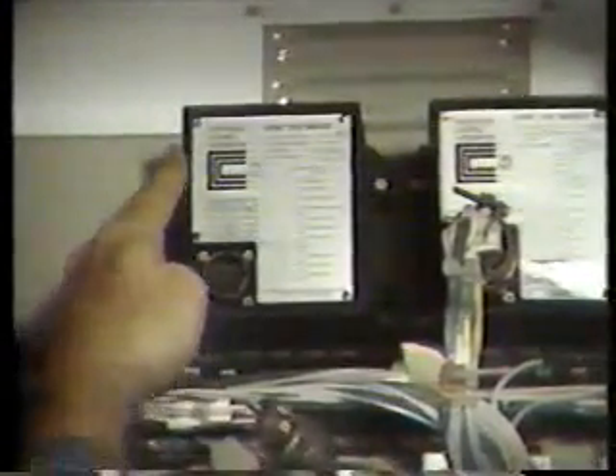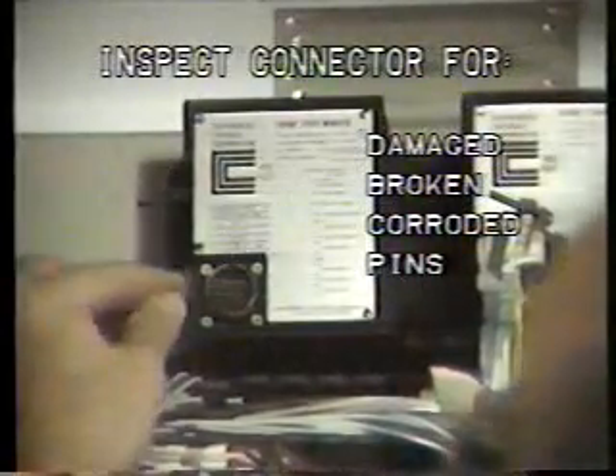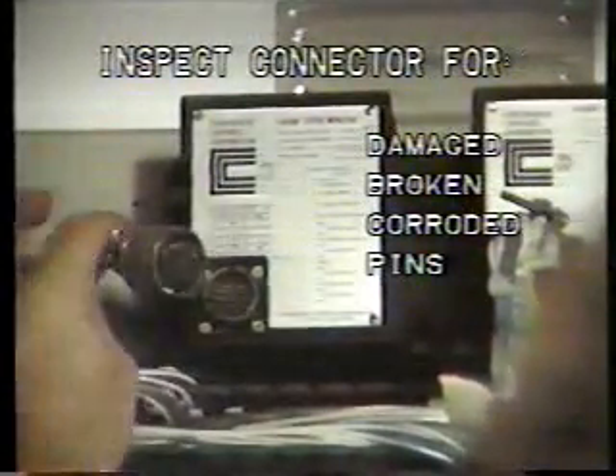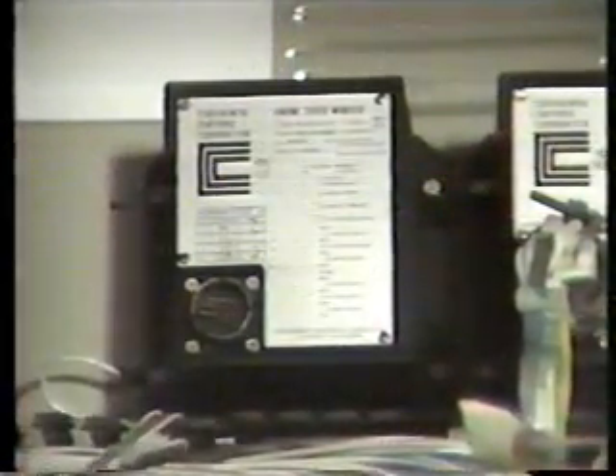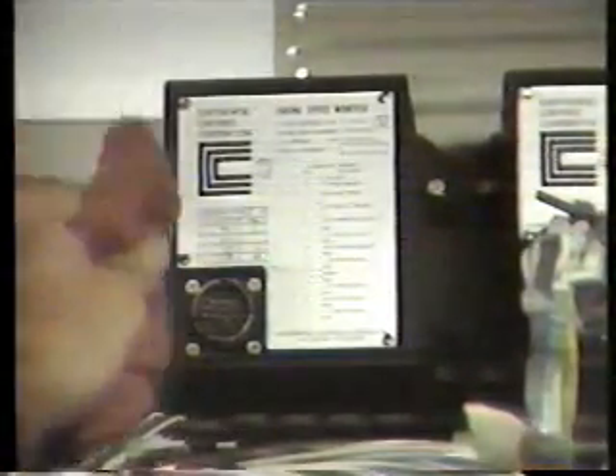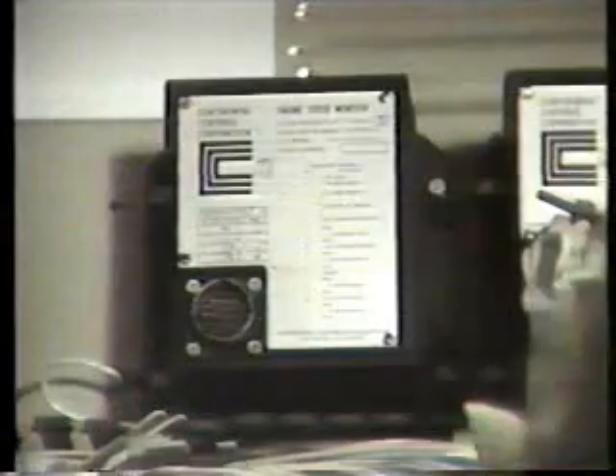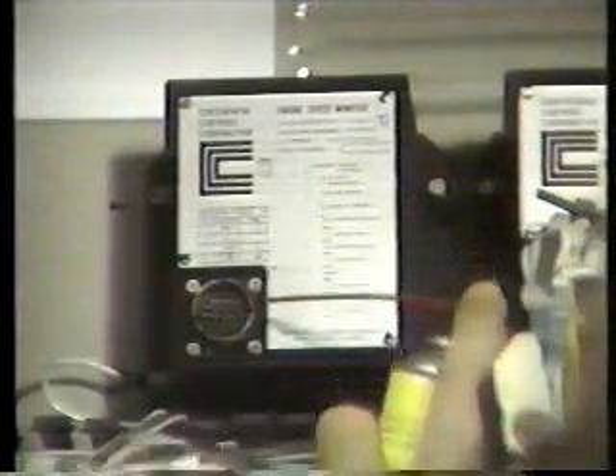With the power off, remove the Cannon plug connector P283 from the control unit Z283. Inspect the engine speed control box for damage and corrosion. Inspect the Cannon plug connections for damaged, broken, or corroded pins and loose or broken wires. Be sure to clean any corrosion if present in the control box or Cannon plug using an electronic parts cleaner if available. Avoid using cleaning agents that leave a residue.